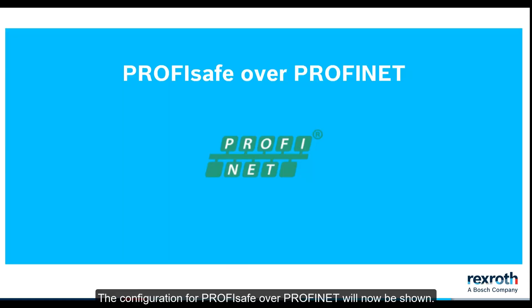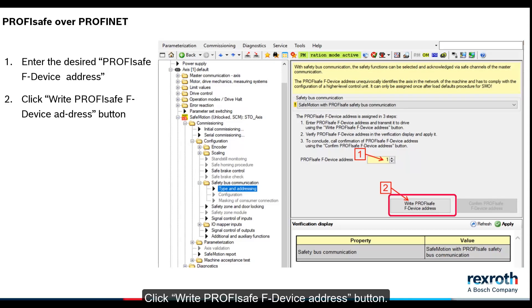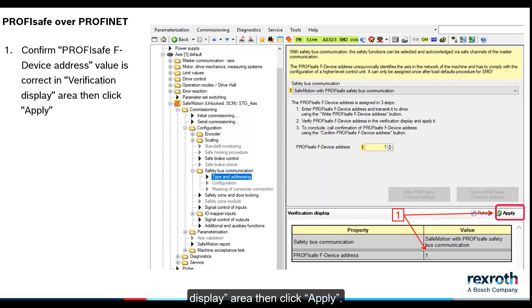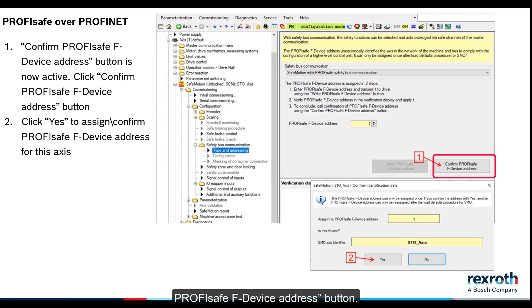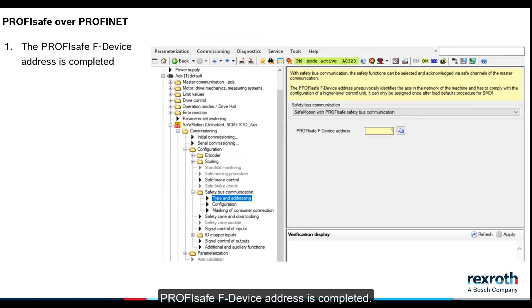The configuration for ProfiSafe over ProfiNet will now be shown. Enter the desired ProfiSafe F device address. Click write ProfiSafe F device address button. Confirm ProfiSafe F device address value is correct in the verification display area, then click apply. Confirm ProfiSafe F device address button is now active. Click confirm ProfiSafe F device address button. Click yes to assign ProfiSafe F device address for this axis. ProfiSafe F device address is completed.